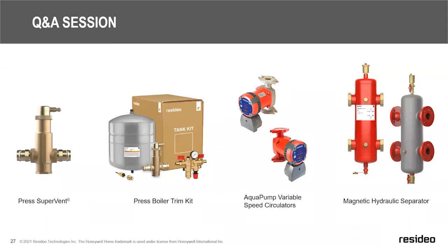It's a proving switch to make sure that valve was open so that you had somewhere for that pump flow to go. Because if you didn't, that pump would basically not have anywhere for the flow to go, and it's what we would call deadheading. Over time, it would basically kill the pump. With variable speed pumps, there are pressure sensors inside that are actually going to identify if zones are open or not. So a lot of people, instead of wiring this into a control, like Mike had mentioned, our HPZCs, our hydronic panels, can actually just put these on a pigtail and plug them into an outlet.